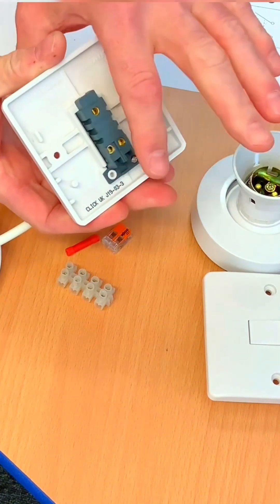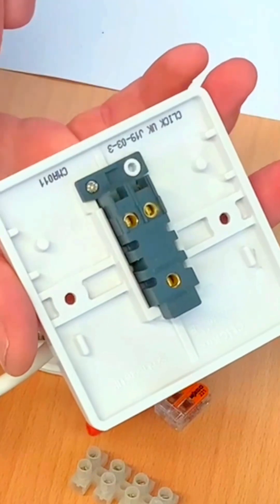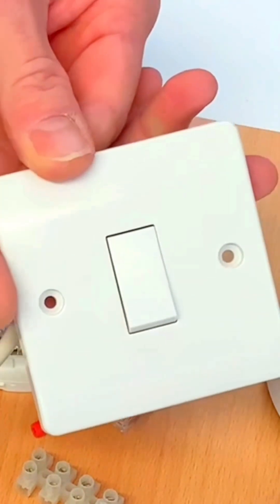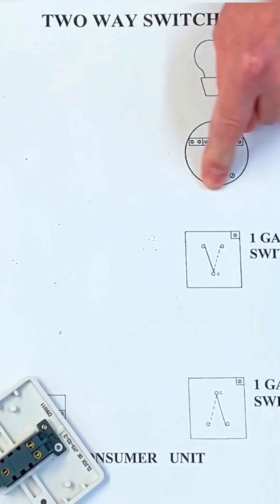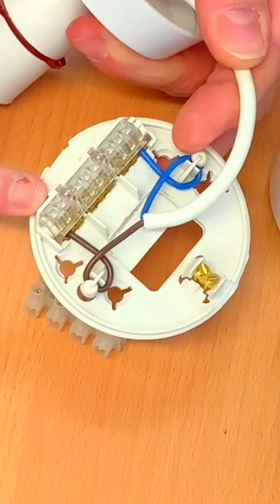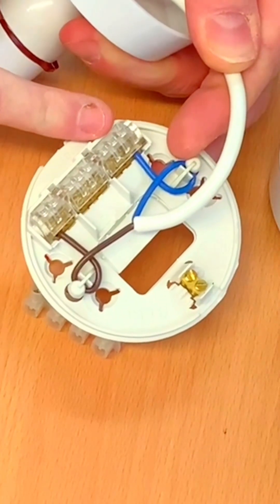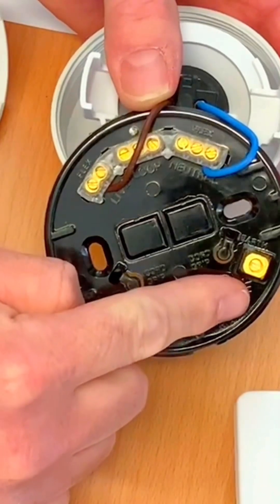It doesn't matter - I could have turned it around. There's common, L1, and L2. It's only important that we get the commons correct, and we'll look at that in the drawing. L1 and L2 can swap as they go between them, but students tend to like to keep them in the same place. So this is a one-gang two-way switch, and we need two of those. We've got here the base of a ceiling rose or pendant, with two terminals for switching line, insulated away from three terminals for the loop, three terminals for the neutral, and a connection for our circuit protective conductors.